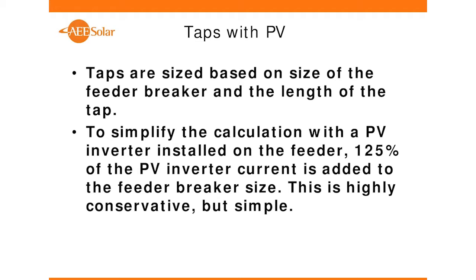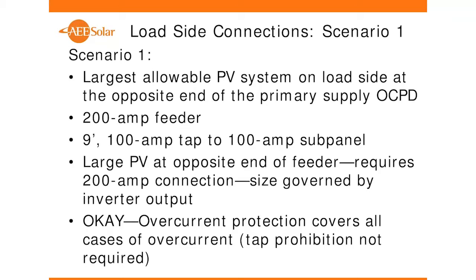And what we're saying is that the feeder breaker doesn't calculate any current coming from the PV, so we just say if you've got a 200 amp feeder and you've got a 200 amp PV, that it would be just like connecting to a 400 amp feeder breaker. And do all your calculations based on that. And that's going to be way better than not doing it at all. Okay, so let's take a look at that. Let's take a look at a scenario here.